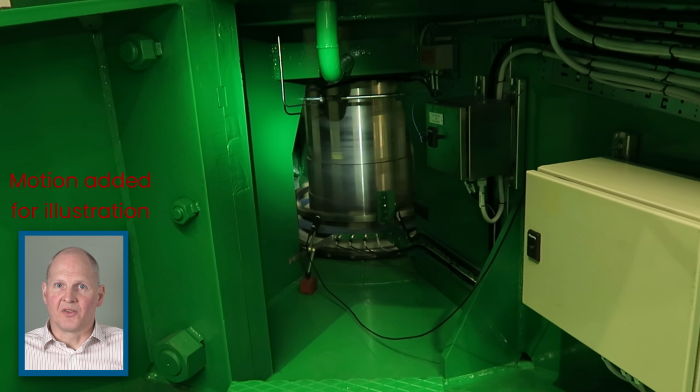If your generator behaves like this, you want to know why. The flux graphs usually contain interesting clues, and this holds true even if the root cause of the problem isn't magnetic. Because problems not related to the field winding often also result in asymmetric flux density, even if the rotor and the field winding are perfect. And here I'll show you two production machines with examples of this.